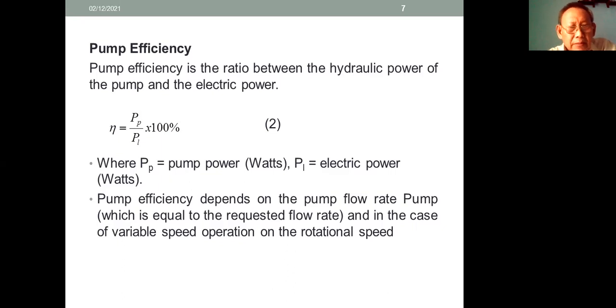η = PP / PL × 100%, where PP is pump power in unit watts, PL is electric power in unit watts. Pump efficiency depends on the pump flow rate, which is equal to the requested flow rate, and in the case of variable speed operation, on the rotation speed.